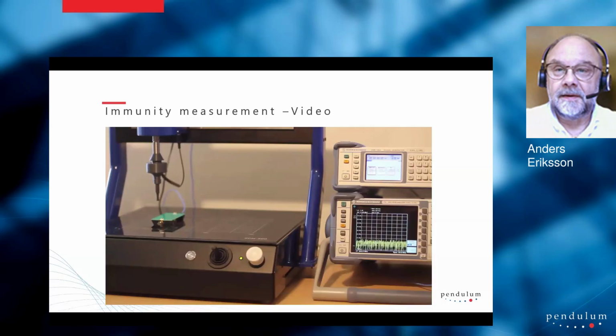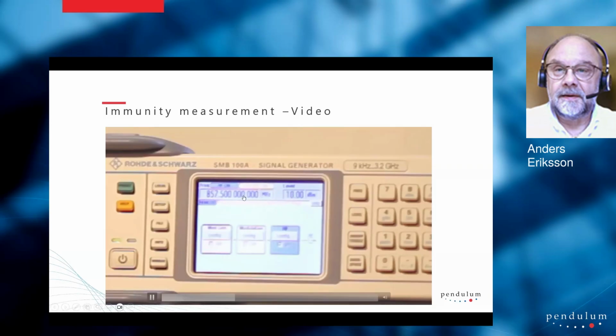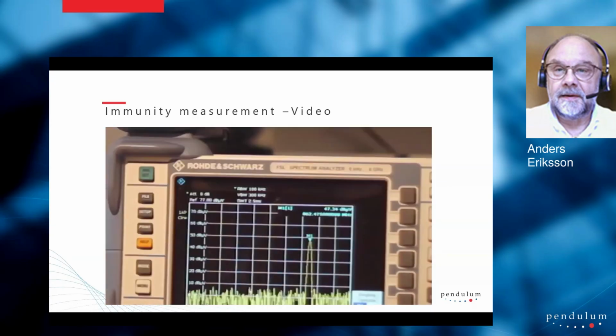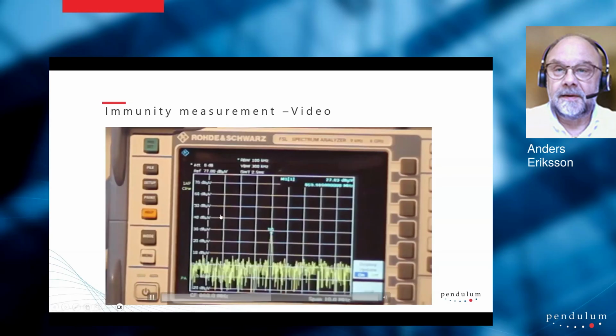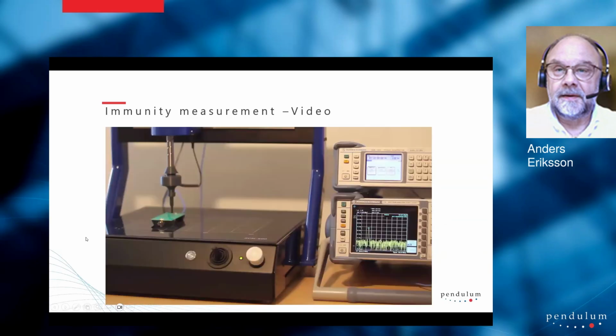We move to the first measuring position, and then we start moving frequency and amplitude, and all the time we measure the health of the DUT. And I will zoom in a bit. Here we are. You can see we change frequency and we change amplitude, and this is the result on the error detection device. You see the peaks stop at 50 dB microvolts. And this is how an immunity measurement is done.